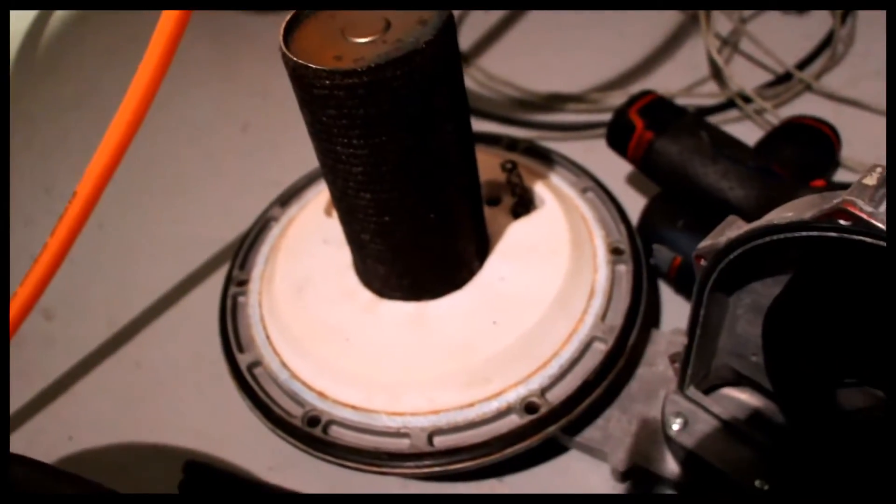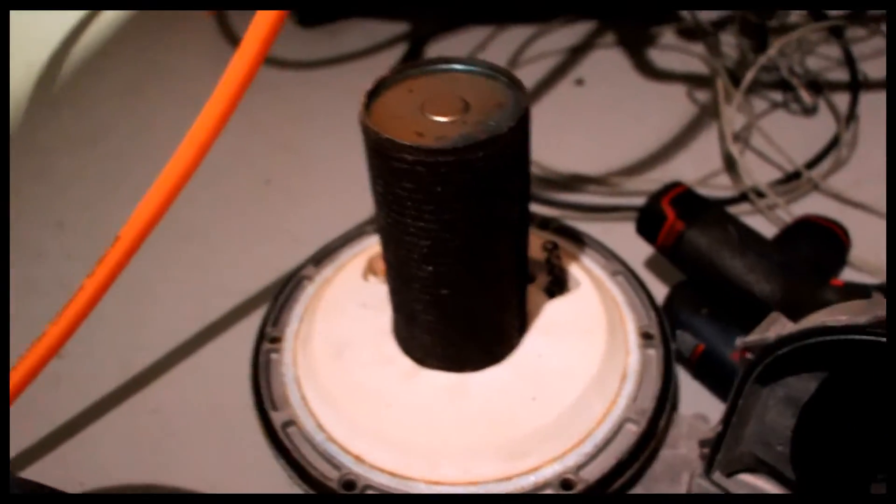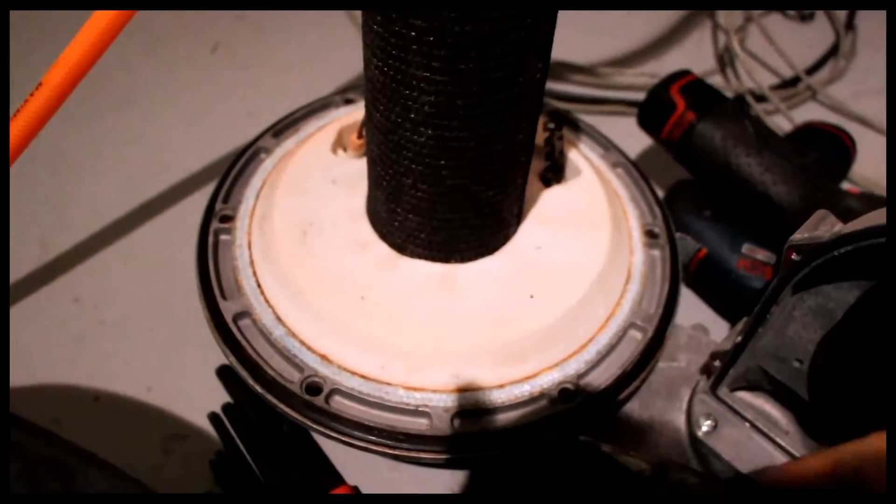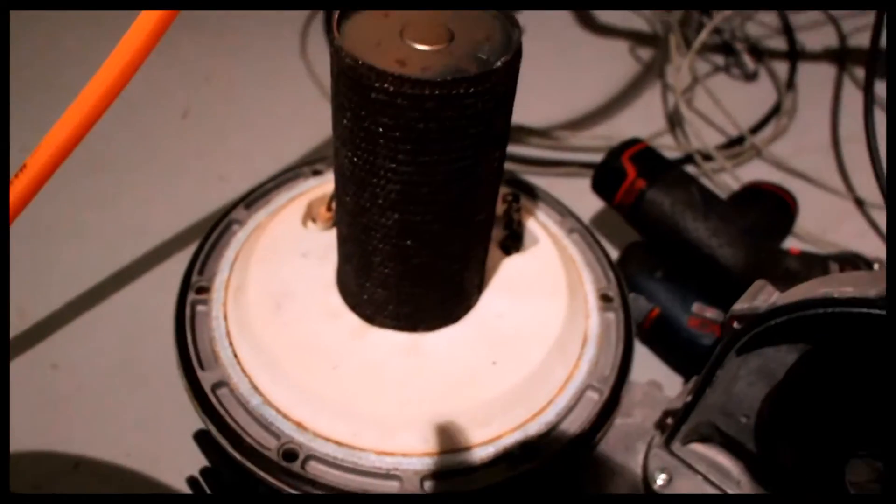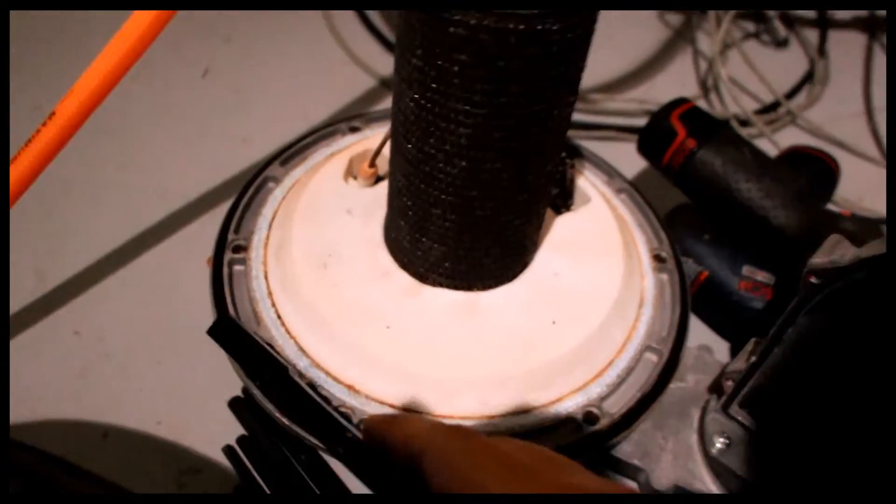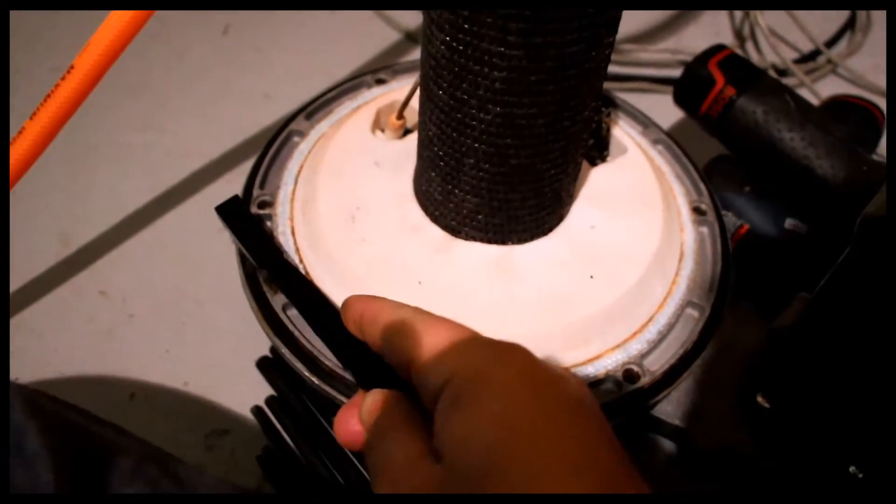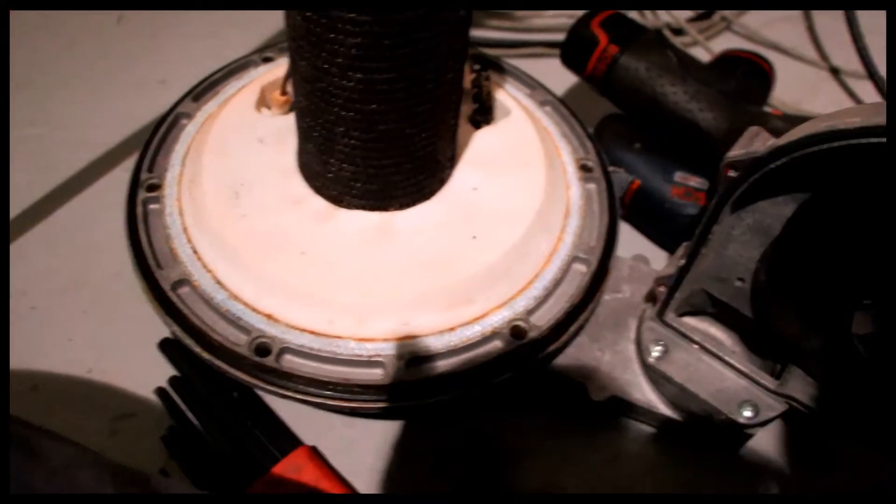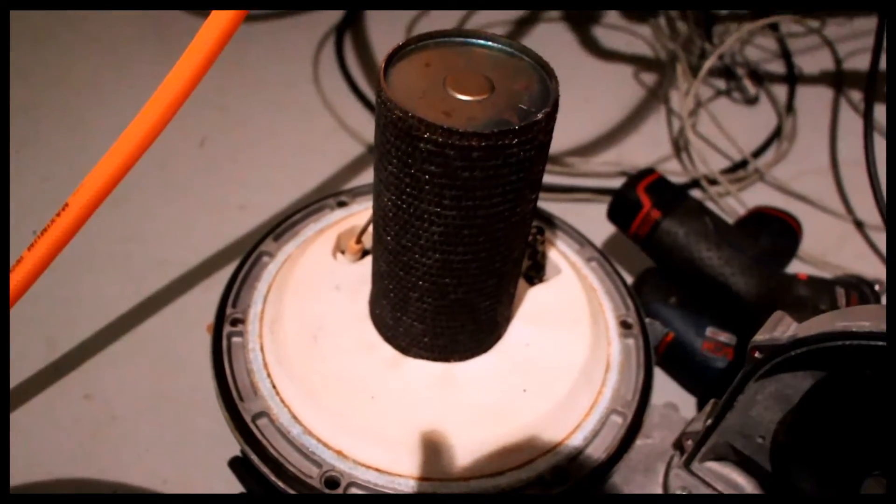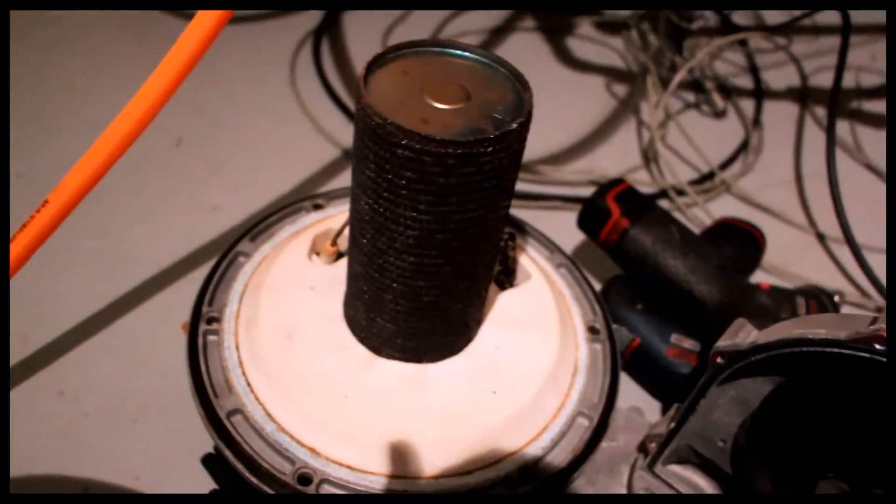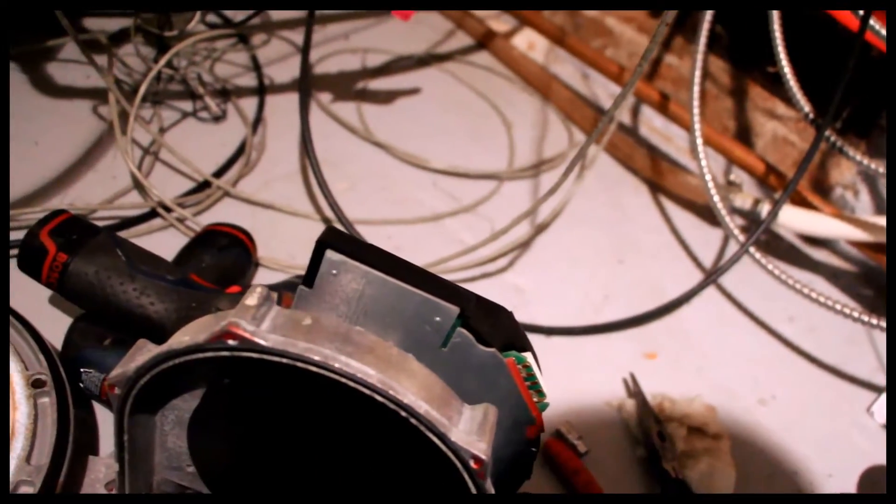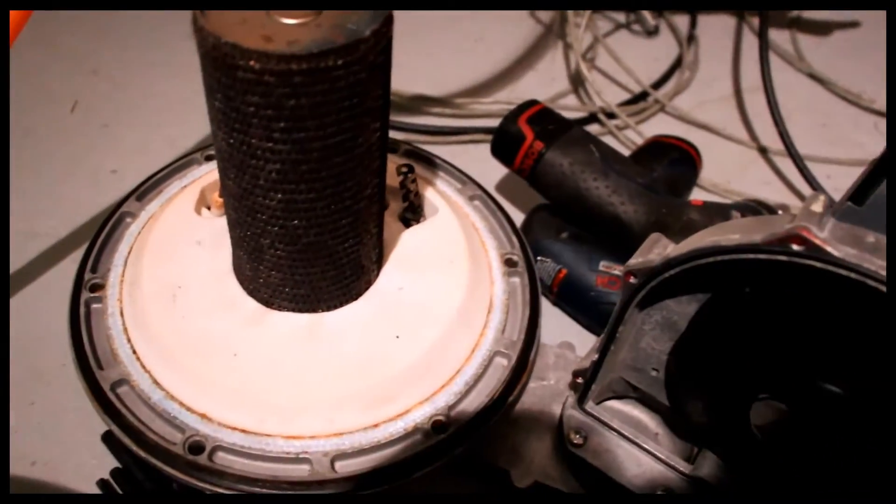Can't forget about the burner. What I did with this was I just gently tapped it. All kinds of black stuff comes off. So I just simply vacuumed that up. The other thing that I did was around, because there's so much junk on the burner there. What I did was I just took the brass brush and I went around this rubber seal. Not the inner seal. But I went around the rubber seal and just kind of knocked off any stuff that's on there. There's a little bit of corrosion around the rubber seal. Probably next time I take this apart I'll want to remove that and give that a thorough cleaning. But no real need for now. I put grease on all the bolts. And now I'm going to reinstall it. Obviously you got to check for leaks and everything.